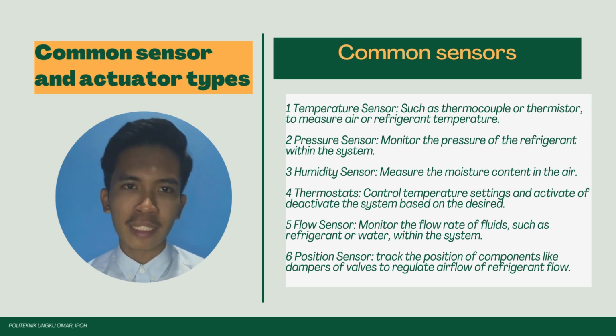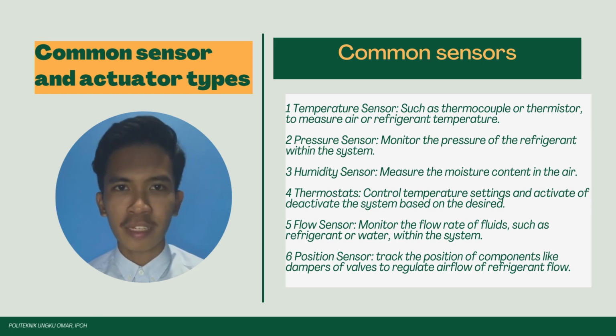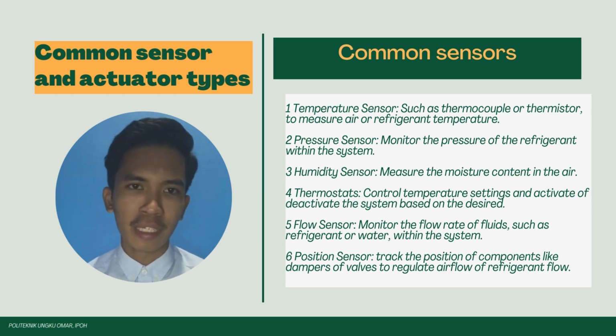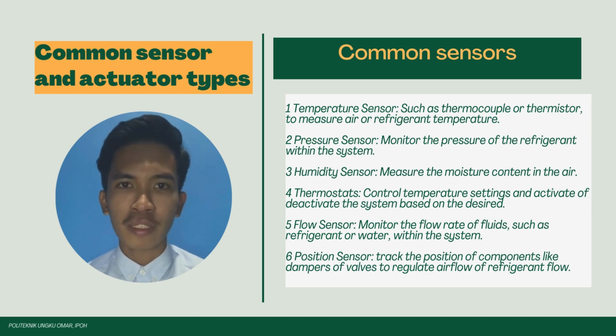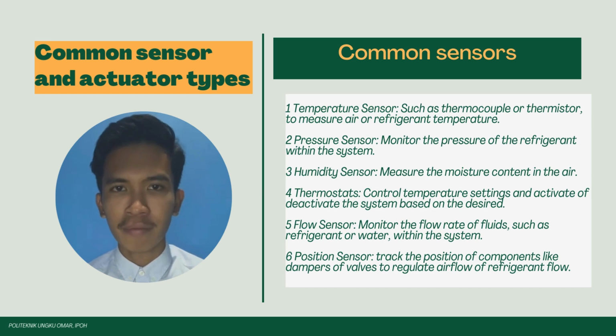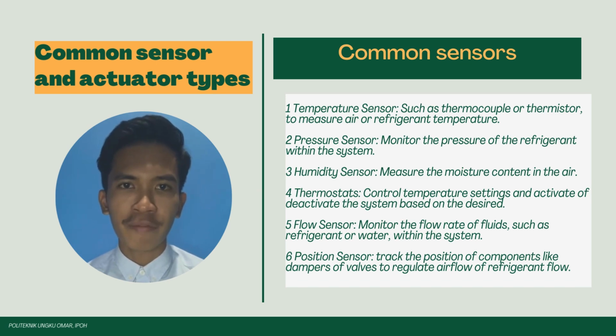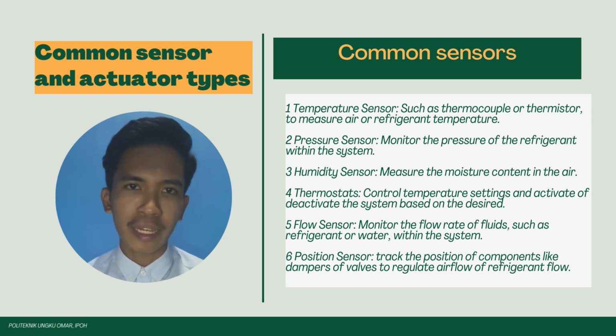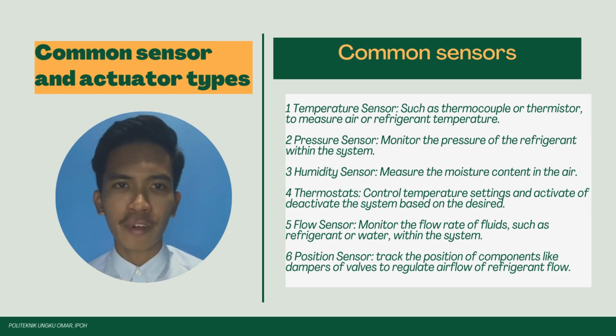Number one is temperature sensor, such as thermocouple or thermistor, to measure air or refrigerant temperature. The second one is pressure sensor, to monitor the pressure of the refrigerant within the system. The third one is humidity sensor, to measure the moisture content in the air. Number four is thermostat, to control temperature setting and activate or deactivate the system based on the desired setting. Number five is flow sensor. It monitors the flow rate of fluids, such as refrigerant or water, within the system. Number six is position sensor. It tracks the position of components like damper or valve to regulate airflow or refrigerant flow.